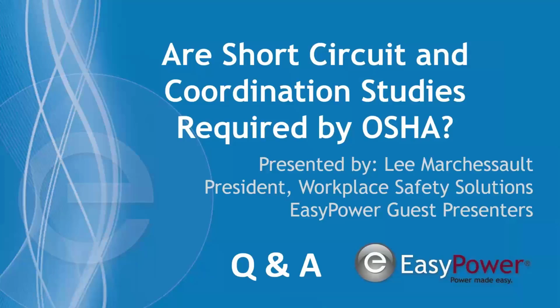This question is open for discussion. What is the maximum incident energy if the range is not definite, such as level 2 is greater than 12 for PPE requirements? I don't quite understand that. Yeah, I'll read that one more time. What is the maximum incident energy if the range is not definite? In other words, such as level 2 is greater than 12 for PPE requirements. I think he's mixing the lookup table with the incident energy levels. Yeah, so you've got tables and labels.